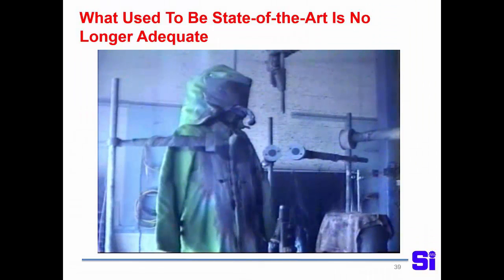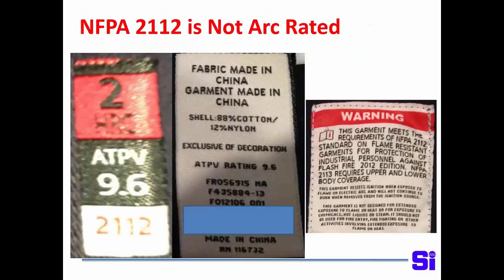It should be marked either on the outside, which most of them are, but I have seen some that are only marked on the inside part of the label. You want to see that it meets ASTM F1506 and NFPA 70E. Now this one's really bad. I'm not sure where this clothing was purchased, but I'm sure they got a really good deal on it.